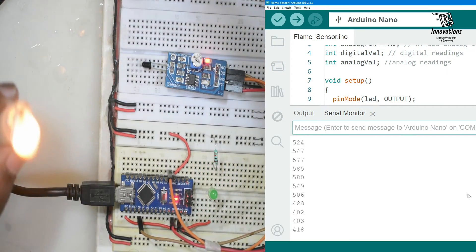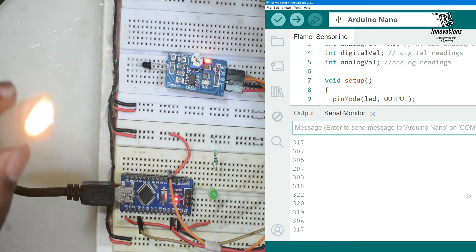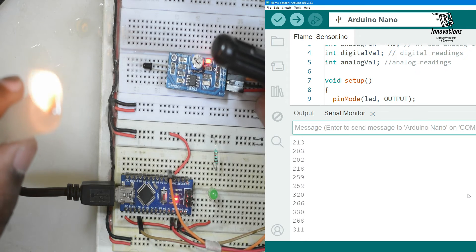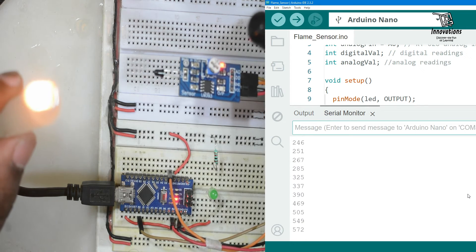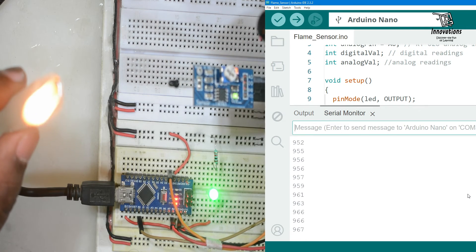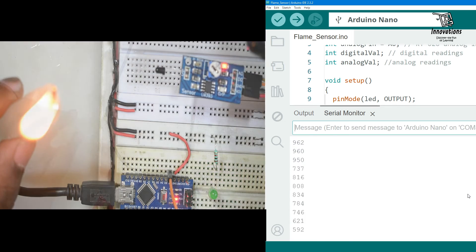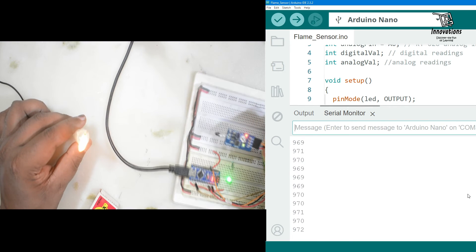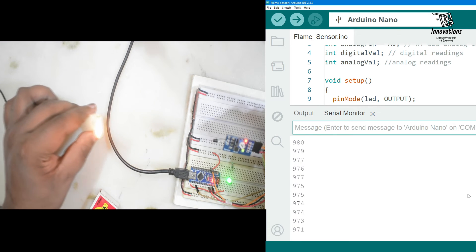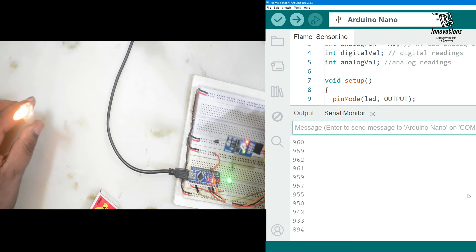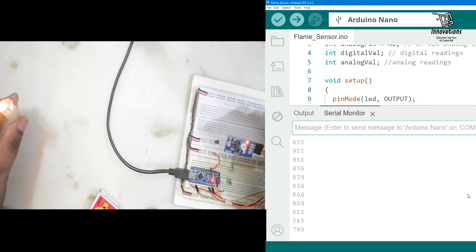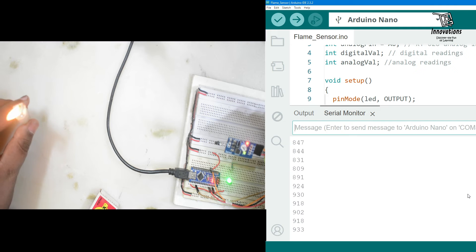As I said the detection angle is about 60 degrees. Since the fire is more than 60 degree angle this is not detecting. But if I turn it towards the fire this will detect the fire. See it is now working. At about one feet it is not detecting the fire.